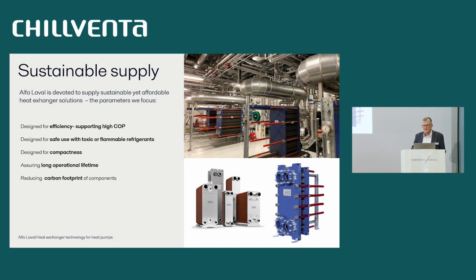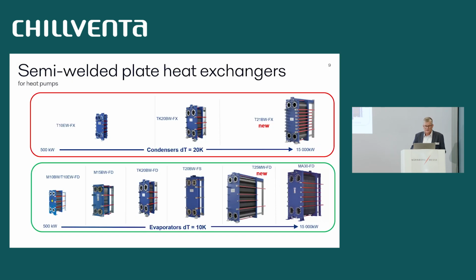I'm going to show you some examples here. I'm going to follow the semi-welded plate heat exchanger, which is this one, where we are continuously developing new products to fit the duties and challenges in heat pumps. Here is the ammonia case, where we have a new condenser that we are launching at this exhibition, the T21 BWFX. It's a 15 megawatt plus ammonia condenser. We have also just developed and are launching a big evaporator, the T25 MW FD. That means we have quite a big range of products, and it is going to keep evolving for different refrigerants.